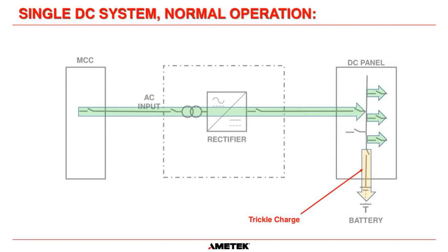So what we're going to discuss now is the power flow. How does the power flow through a DC system? And once again, there's a lot of confusion as to why we have chargers or rectifiers connected to batteries. A lot of people think that their design is to supply power to the critical loads. And in truth, in 99% of cases, the only reason we have a rectifier or charger here is to keep this battery charged. So when we do have a power failure, then the battery is fit for service and will supply the load circuits. It's only there to keep the batteries charged.